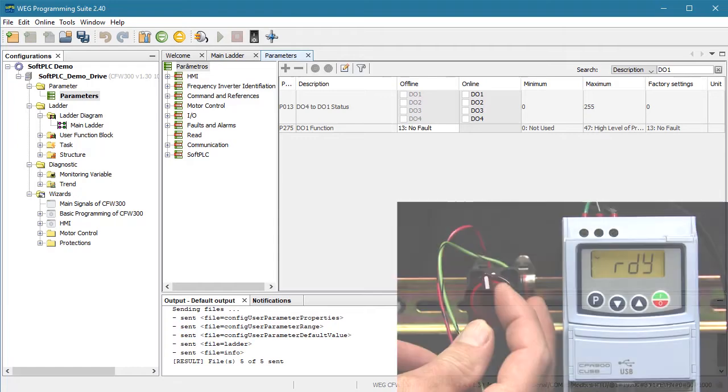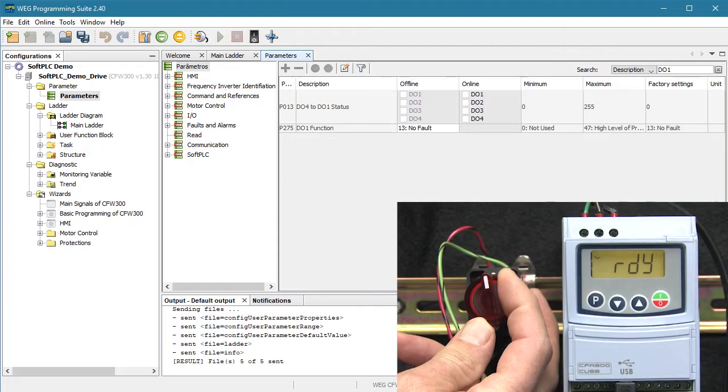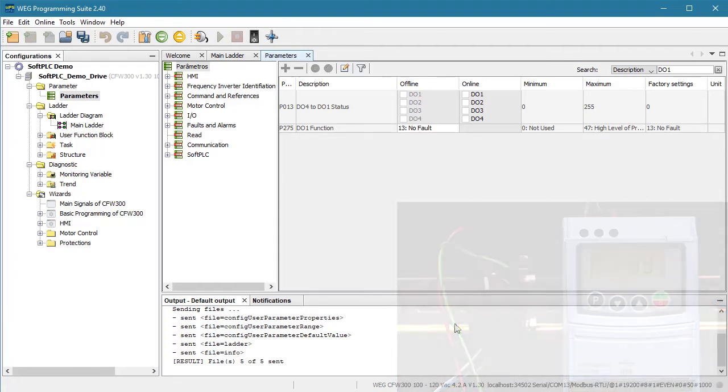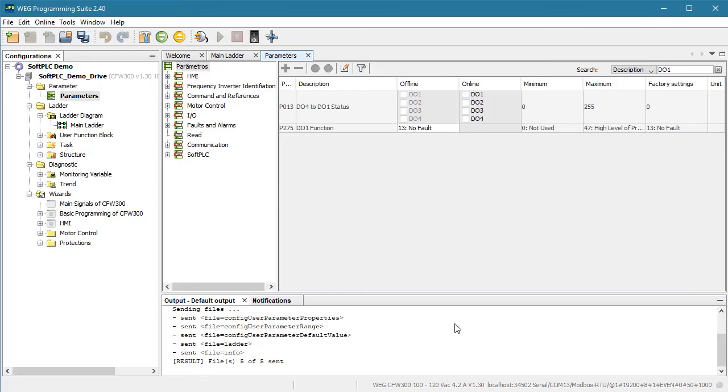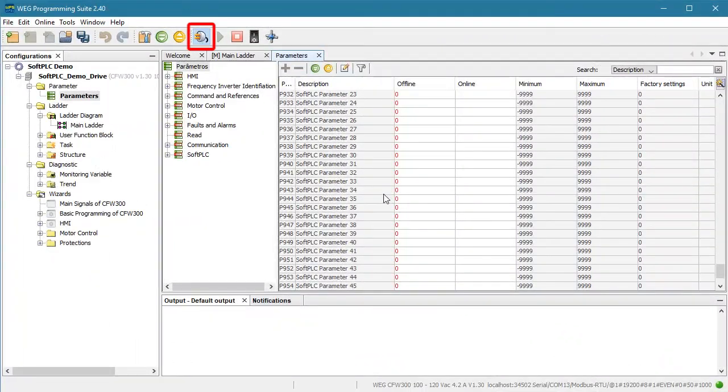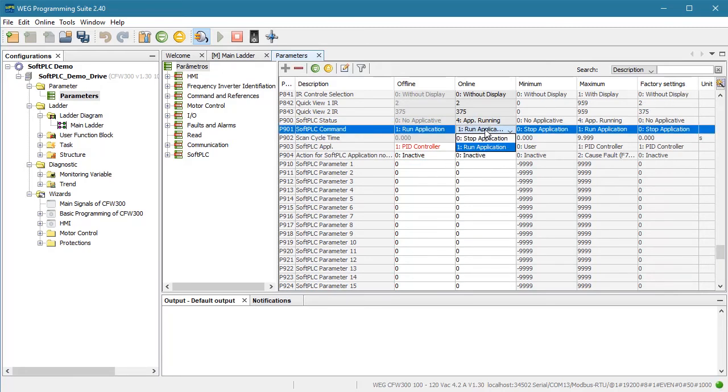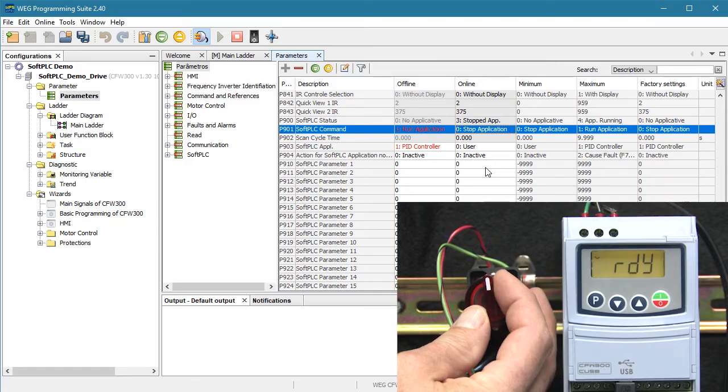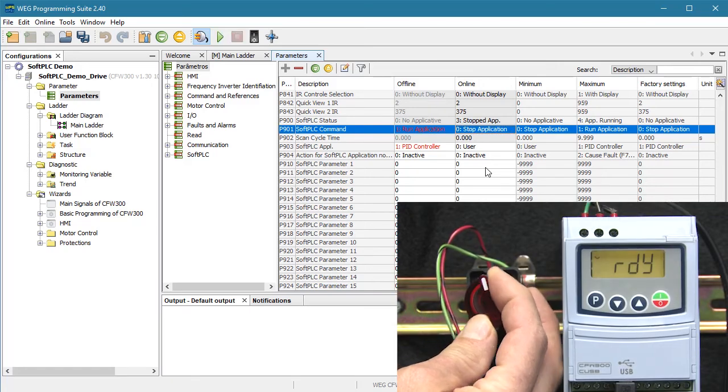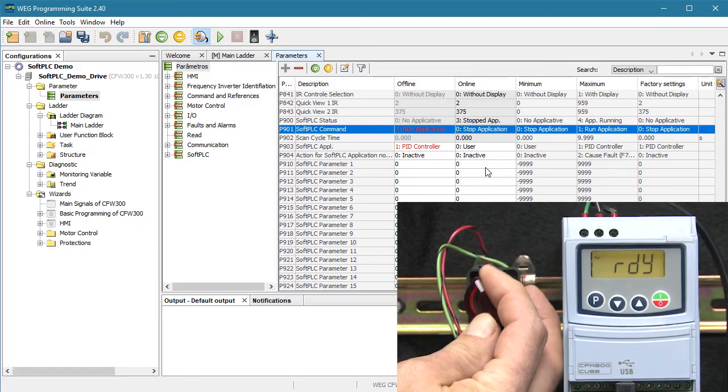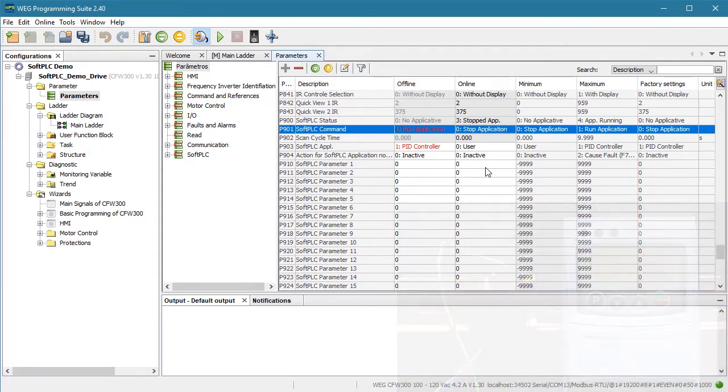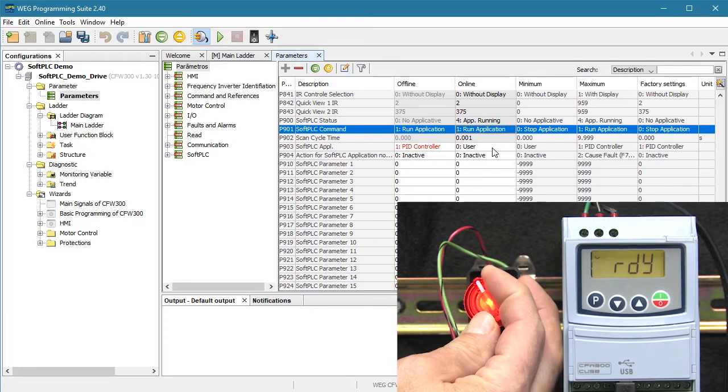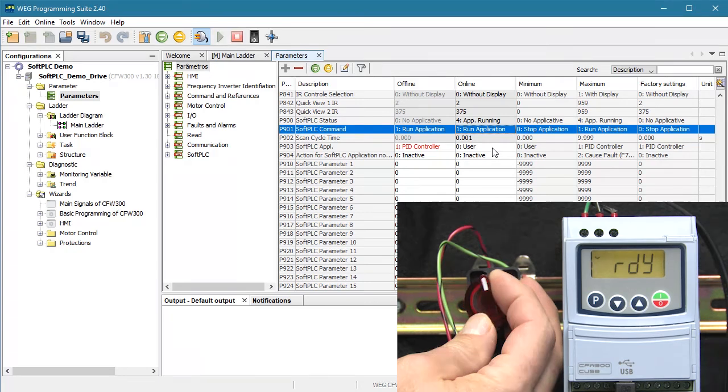If I reach over and flip the switch, the soft PLC sees the switch toggle and then sends it back out to control the light bulb. Exactly what we expect. How do you know that I didn't just connect the switch directly to the indicator? Well, if we reconnect to the drive and go to parameter 901 and set it to a zero to stop the soft PLC, give it a second to take, looks good. And now try to flip the switch. Ah, nothing happens because the soft PLC is no longer passing the input switch signal to the digital output. Let's change parameter 901 back to a 1 to get the soft PLC running again. And sure enough, everything is back working again.